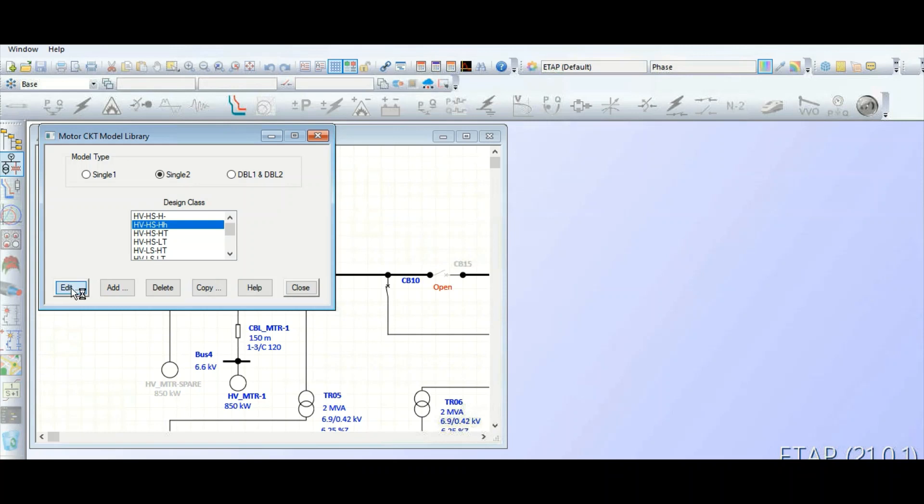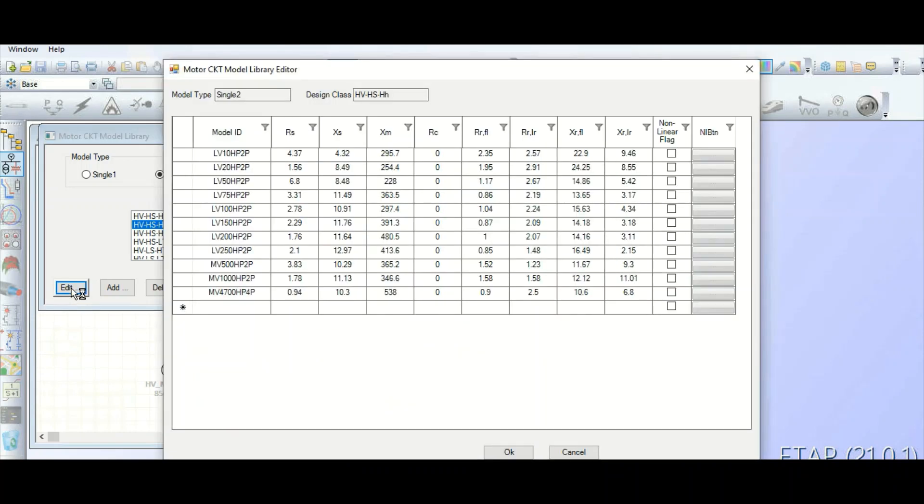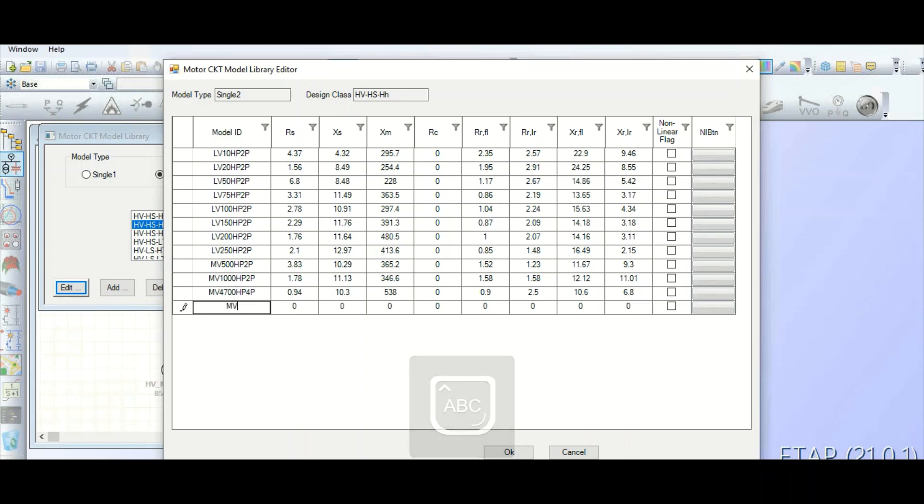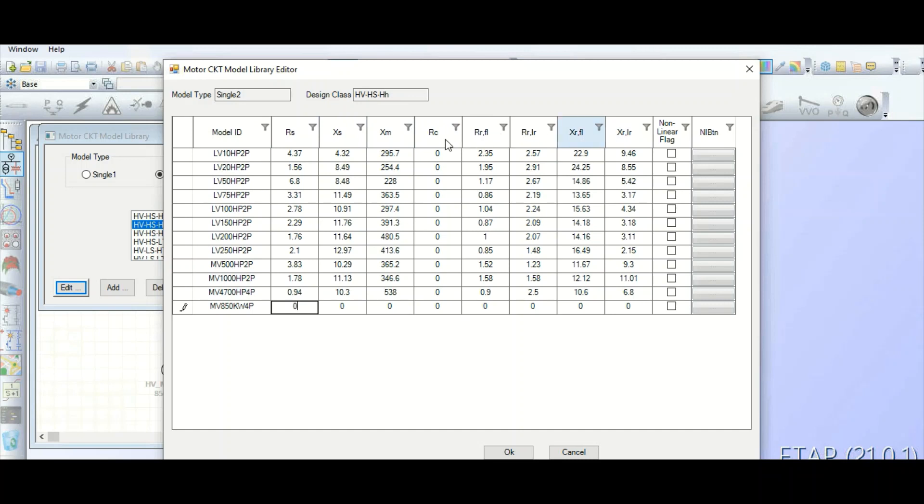Now edit. You can see the star mark, so you need to create this model ID based on your requirement. Suppose this is 850 kilowatt motor, so definitely it is MV motor. I will rename it - I will give the name MV 850 kilowatt four pole motor. If you have the motor electrical parameters - resistance and reactance value of stator, rotor, and magnetizing circuit from the motor manufacturer data sheet - you can fill this data over here.